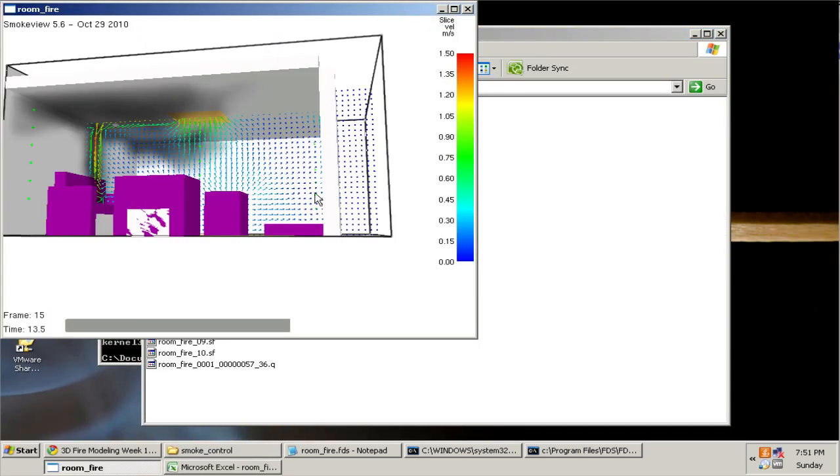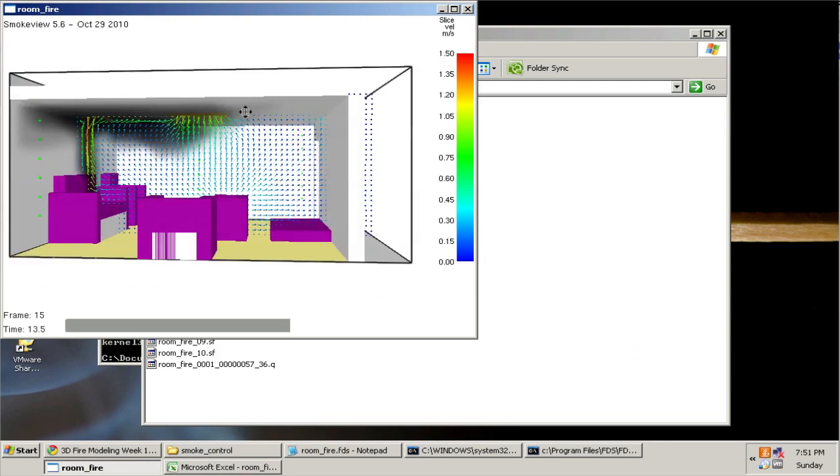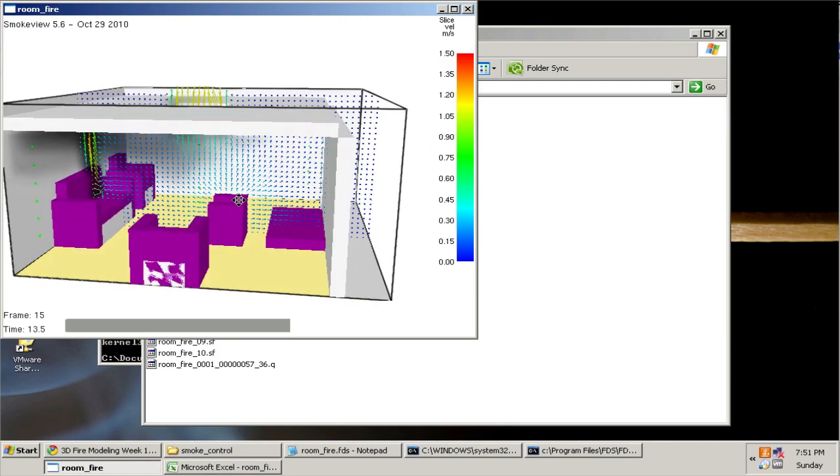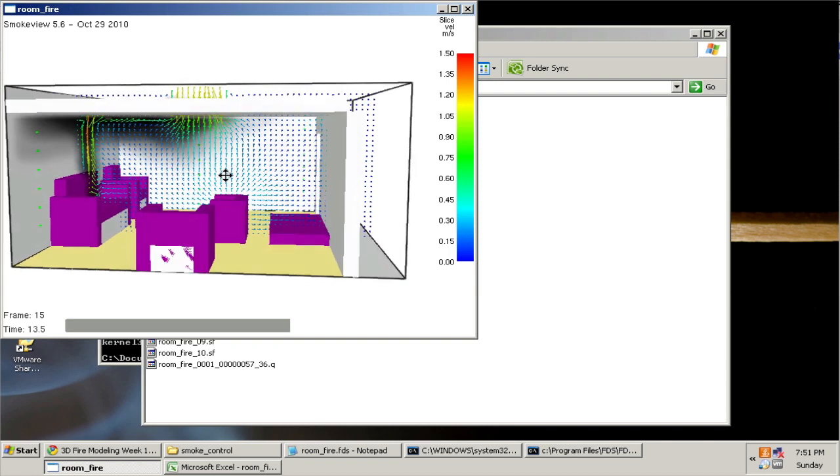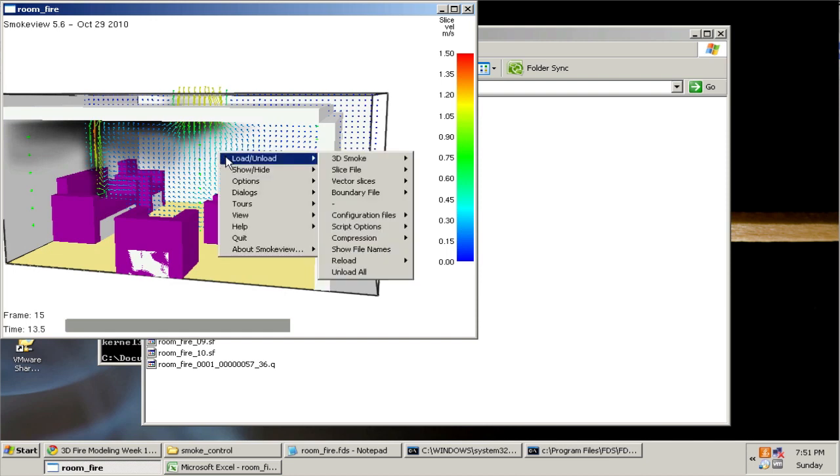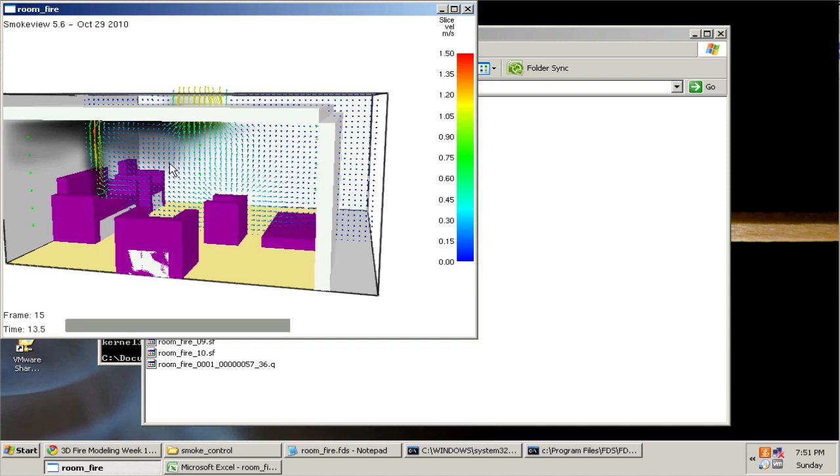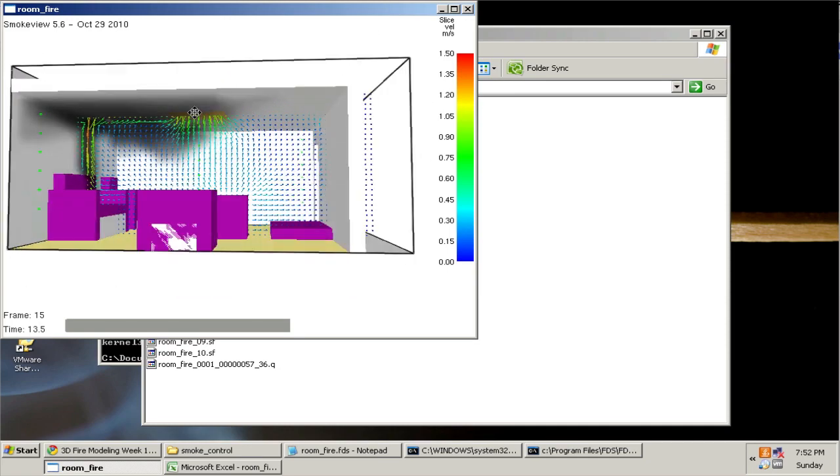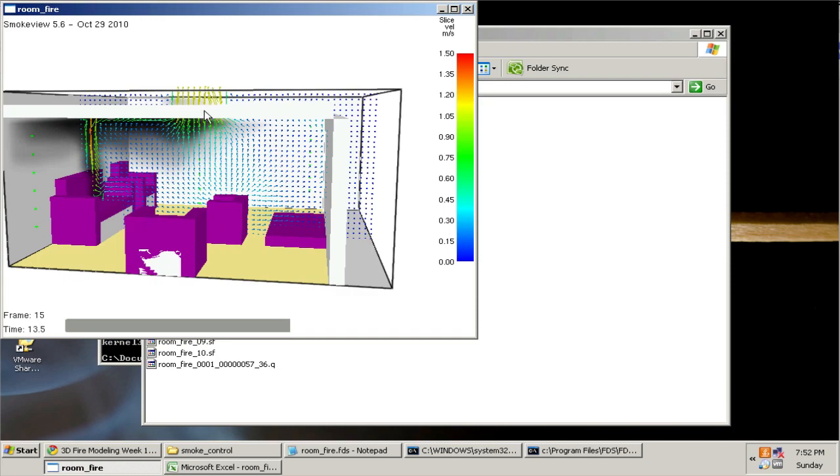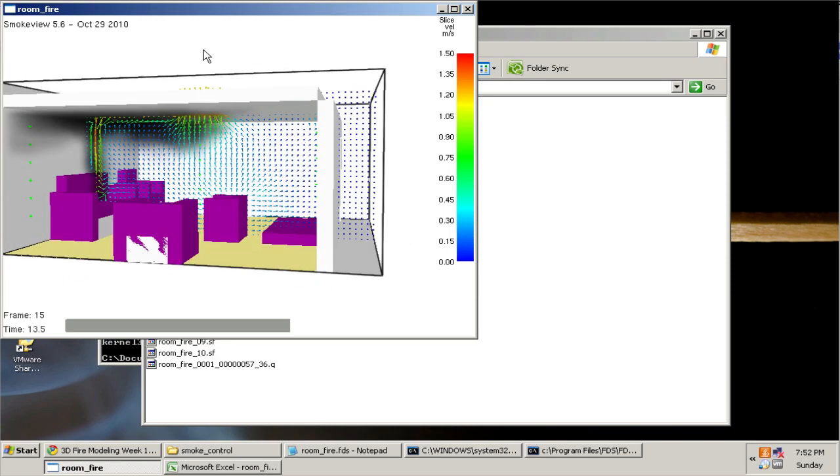The last thing I'll mention is that when you do open up fans and vents like this, you do have to be careful of numerical instability, which happens when you get extremely high velocities that may be non-physical. The code may stop with the error numerical instability. To mitigate that, it dumps out a plot 3D file that you can get to in the load/unload menu. I don't have one right now because that crash didn't occur, but I can look at the plot 3D file and see if in fact that's where high velocities are occurring. If so, I could look at a fan ramp or I could look at a different way to model that that wouldn't result in such a high pressure differential between the inside and the outside.